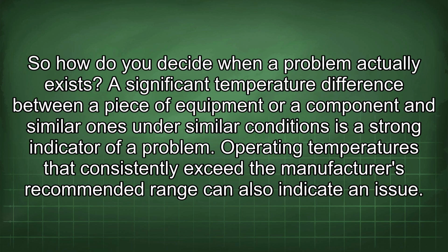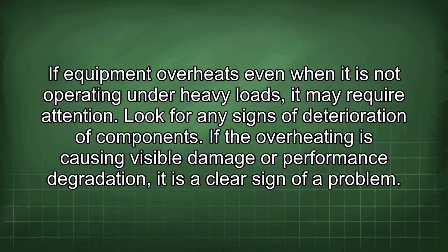So how do you decide when a problem actually exists? A significant temperature difference between a piece of equipment or a component and similar ones under similar conditions is a strong indicator of a problem. Operating temperatures that consistently exceed the manufacturer's recommended range can also indicate an issue. If equipment overheats even when it is not operating under heavy loads, it may require attention. Look for any signs of deterioration of components. If the overheating is causing visible damage or performance degradation, it is a clear sign of a problem.